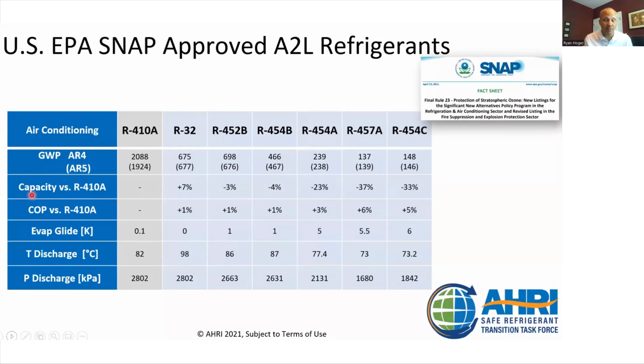From a capacity standpoint, how many BTUs of energy could we shove into a pound of refrigerant? R32 can move a little bit more energy than 410A could move. R454B moves a little bit less energy than 410A could move. That doesn't mean equipment will necessarily be more or less BTUs on the label. It depends on other factors besides the refrigerant itself, coil surface area, etc. But just from a pure refrigerant discussion standpoint, that's the deal there.